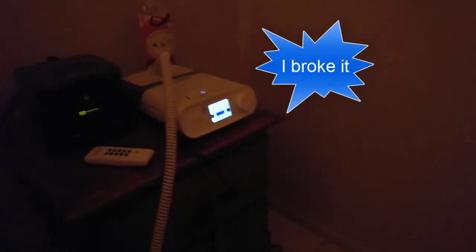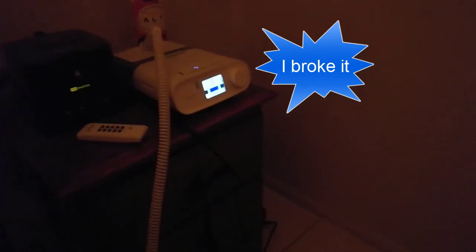I've got to say, ooh, I think I broke it. So the cough test is when you cough with a mask on and you send a big pressure wave down the hose. I don't know whether you heard it, but a second note came into the inspiration expiration after I did the cough test, and I noticed a slight pressure drop off. That means there's a seal dislodged somewhere. So I would say that the Philips is not as robust as the Fisher and Paykel. It looks like I may have damaged it with the cough test.